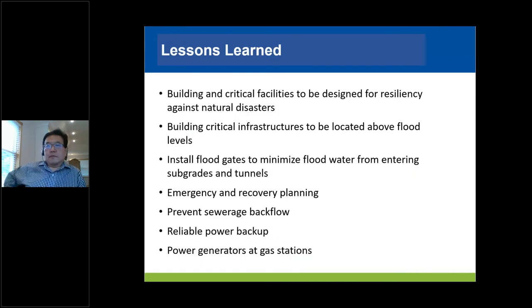So the lesson learned from Sandy is that buildings and critical facilities need to be designed for resiliency against natural disasters. For many buildings, we have to make sure that critical infrastructure, such as generators, mechanical systems, emergency generators, switch gears, and transformers, need to be above the floodplain levels, to ensure these buildings can be brought back to service in a relatively short period of time and that sump pumps are working when they need to be.